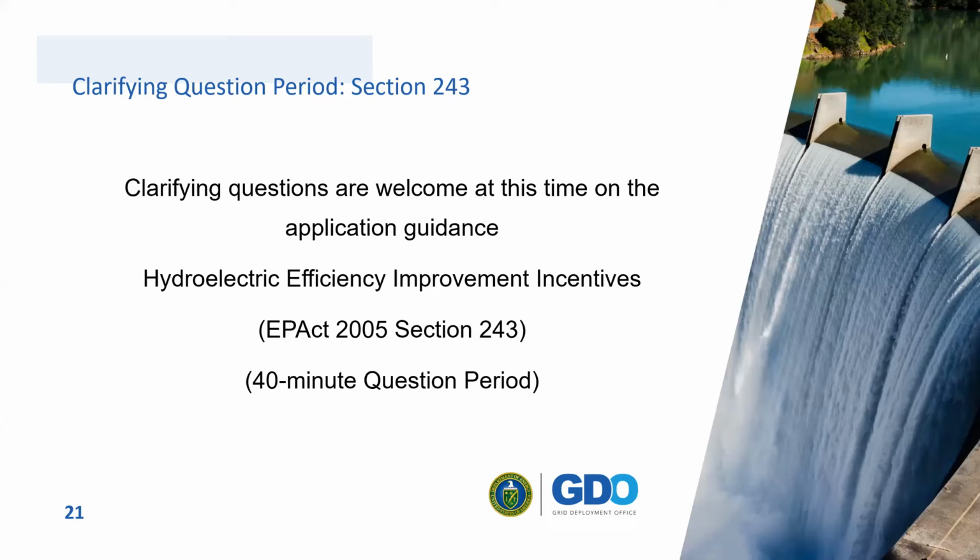Yes, this kind of goes back to the question about nameplate data. As you look at the spreadsheets that were provided and the historic data that we're to provide, that's flows, head, produced power, when you calculate efficiency using those numbers, you'll end up including any degradation, say to a turbine runner due to pitting or corrosion or whatnot. So that's really not operating necessarily at nameplate capacity. I guess I'm a little bit confused about what the base case would be, if it's really the historic, what we've been doing and what the unit is performing at within the last 5 years, or if we're projecting back and saying what that unit should be if it was back in new condition.